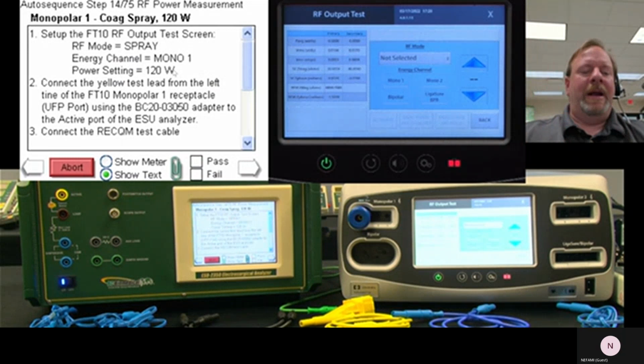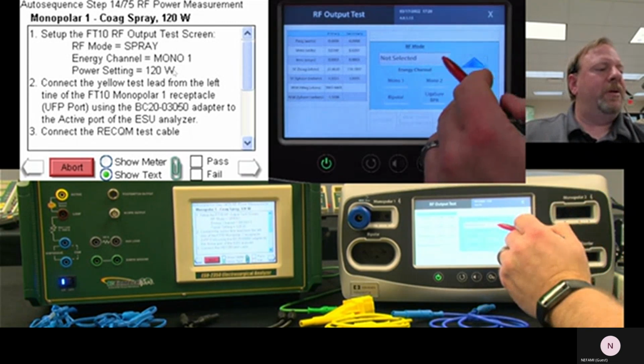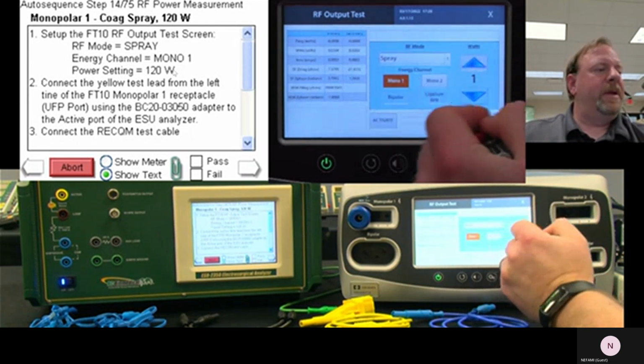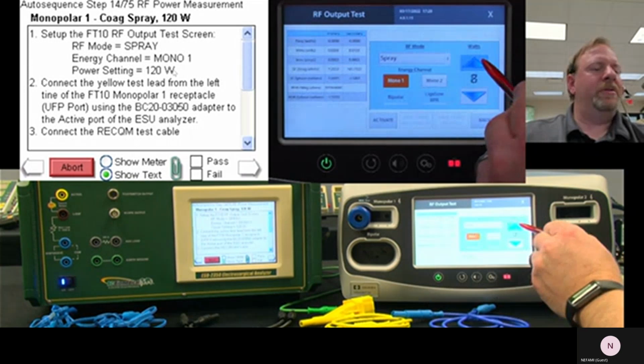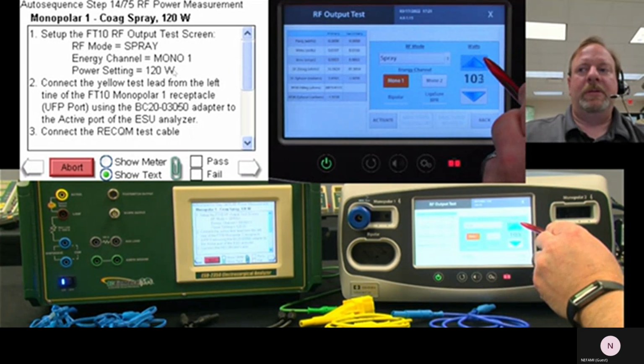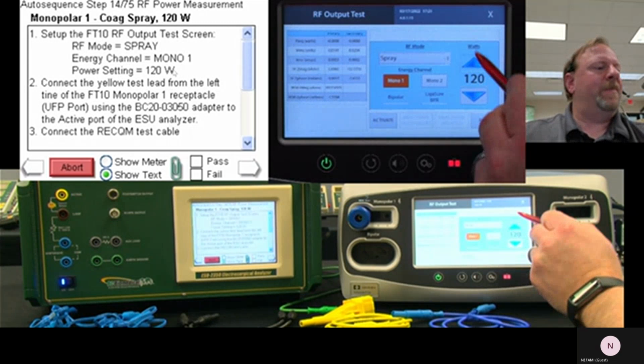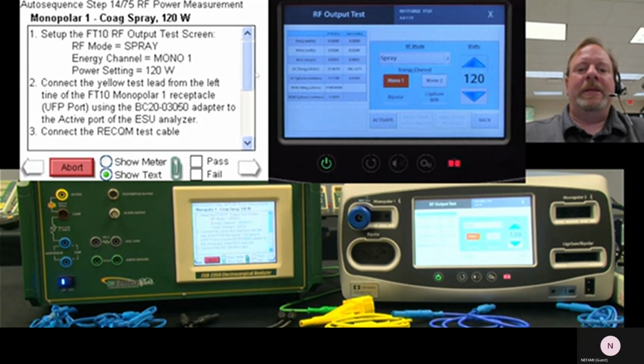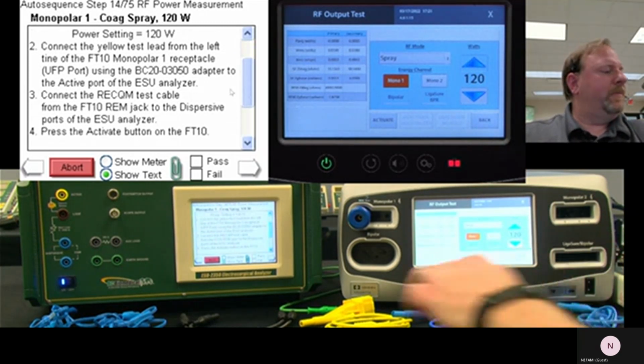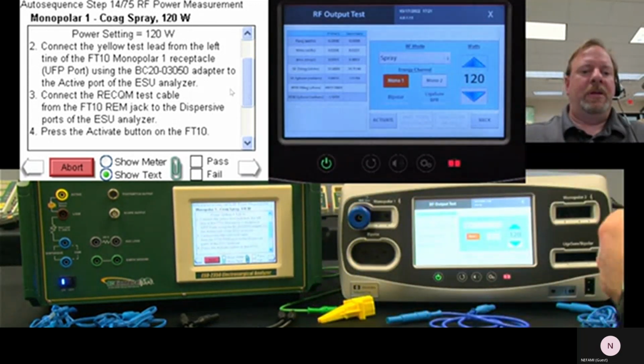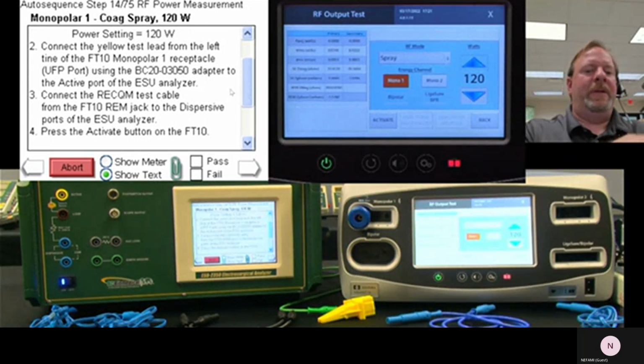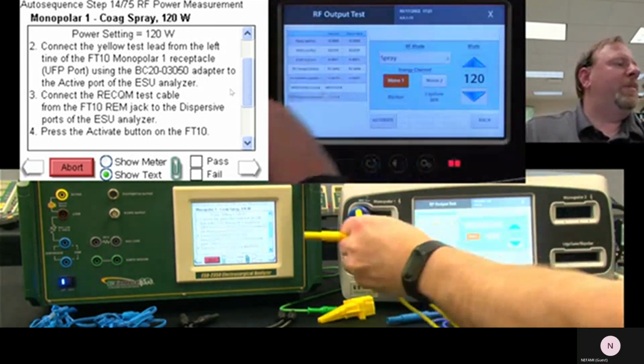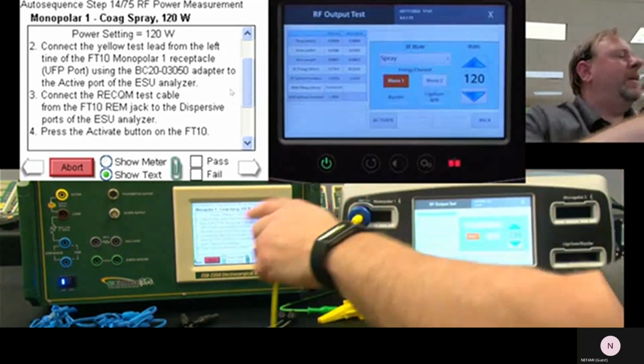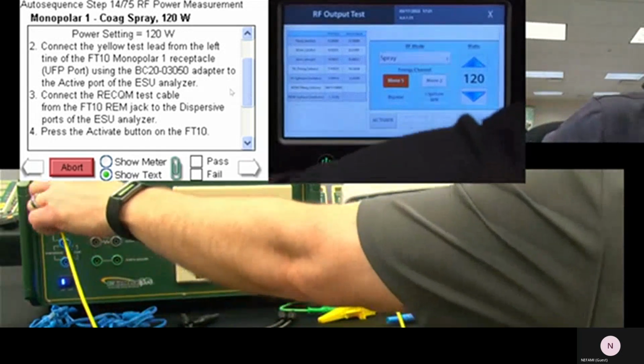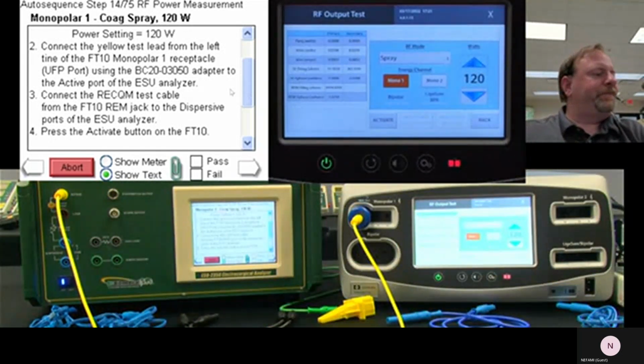So my instructions are right here on my screen. What do I do? First, set up the FT10. So we're going to go to spray, and we want monopolar 1, and we want 120 watts. So easy thing there is that's the maximum output. And then it's going to tell me how do I do my connections. Yellow cable going from the left tine of the monopolar 1. So here's monopolar 1, here's the leftmost connection, and that's going to go to active on the 2350.